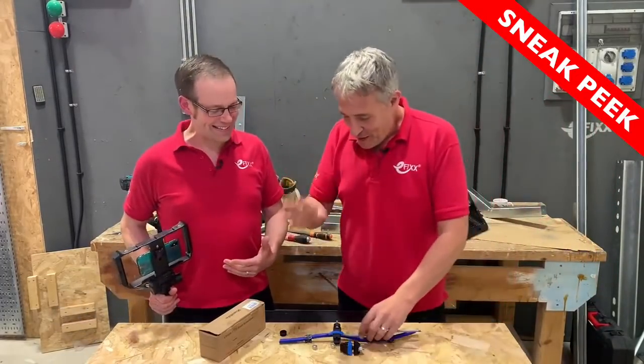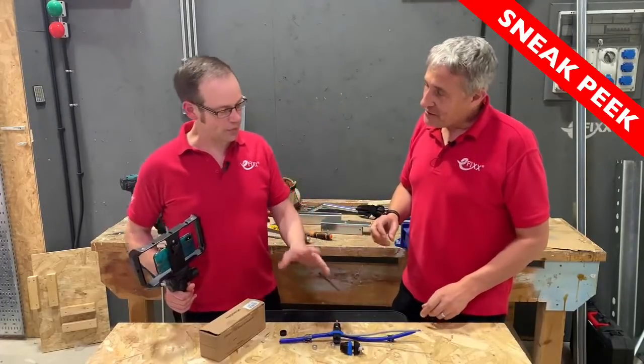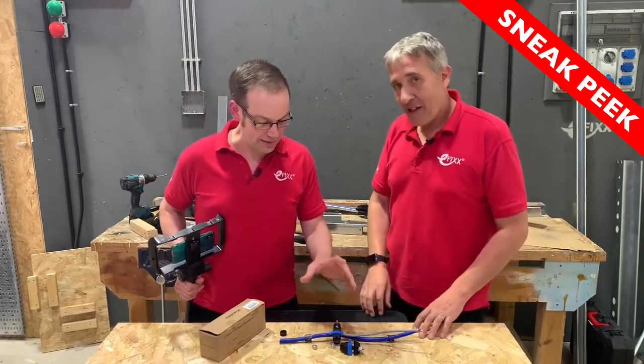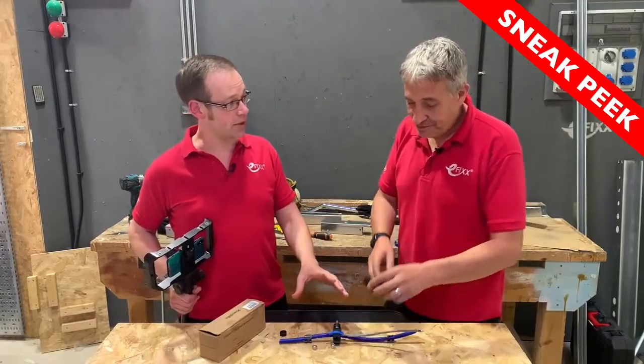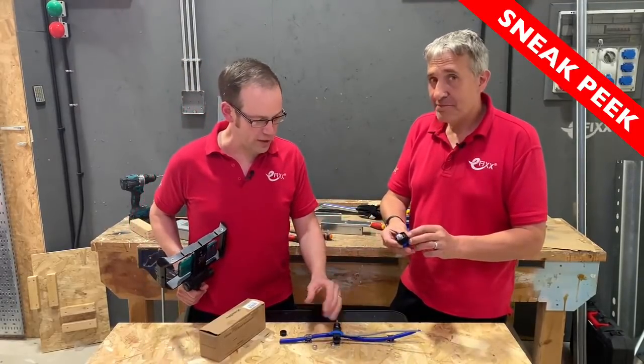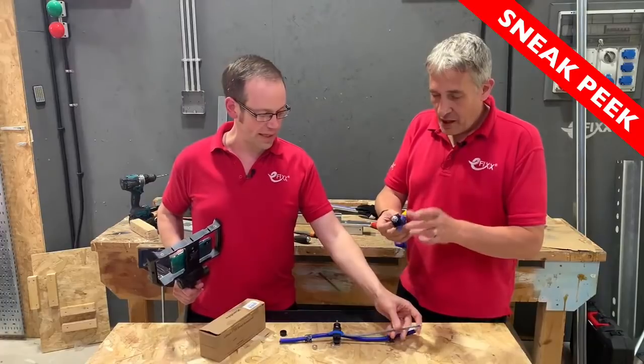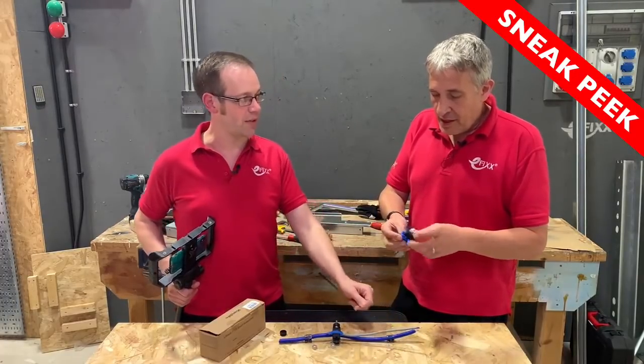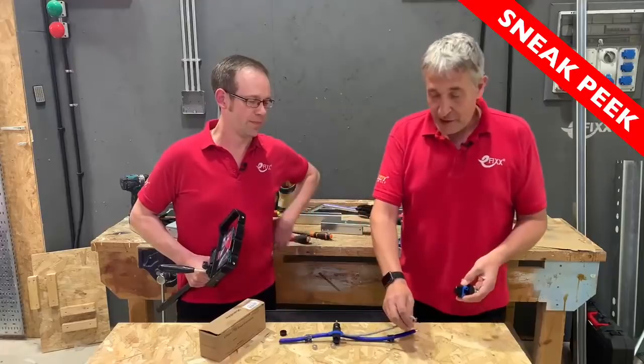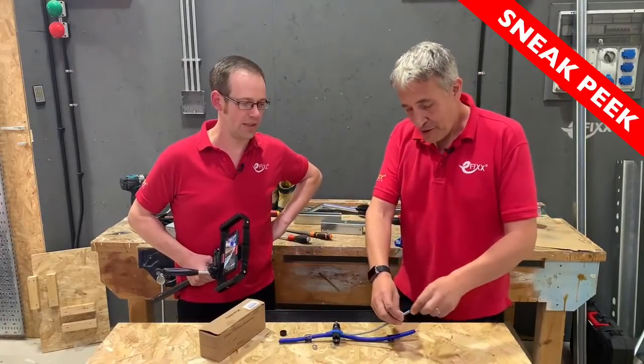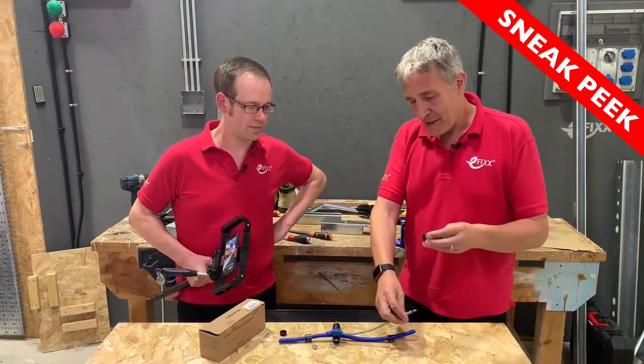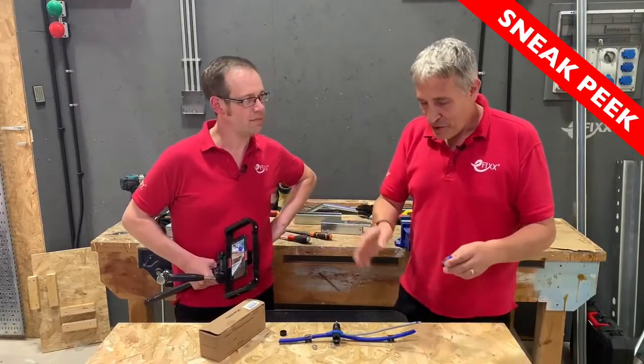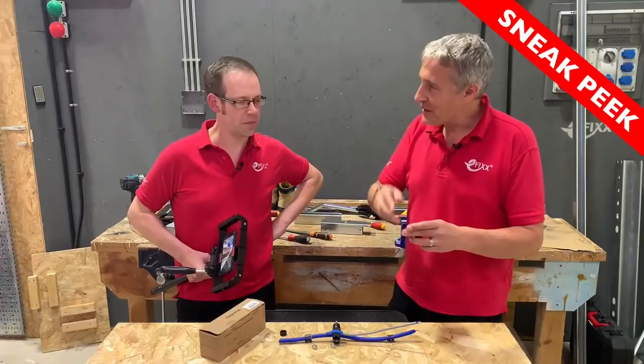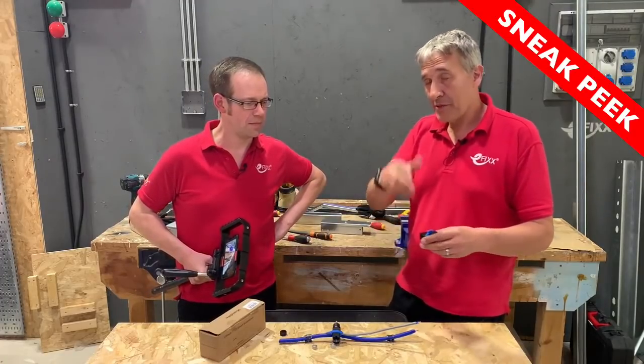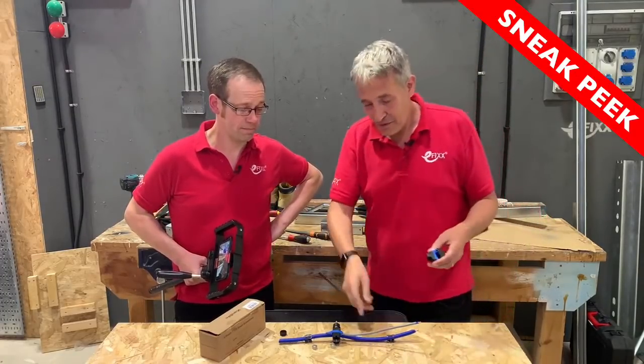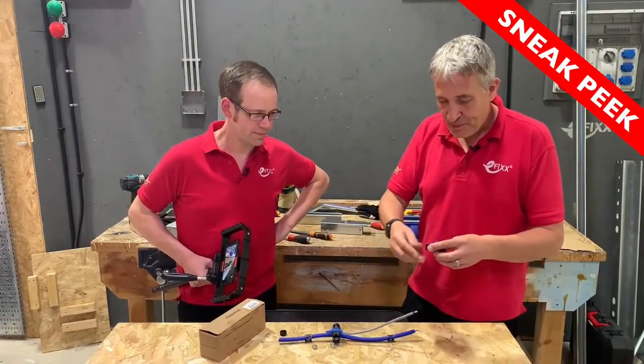We're going to have to do some more investigation, because I think we've got a couple of reservations. What they're designed to do, they do brilliantly, and they've been tested for that and work perfectly for it. But what's the major difference between the cable this is designed for and the cable we've used it for here? This is a double insulated cable, so we've got an outer mechanical protection, then the insulation inside. I don't think the designer of that was thinking that's what it's used for, unless someone can tell me these bundled cables have that type of insulation. So that was the first concern.